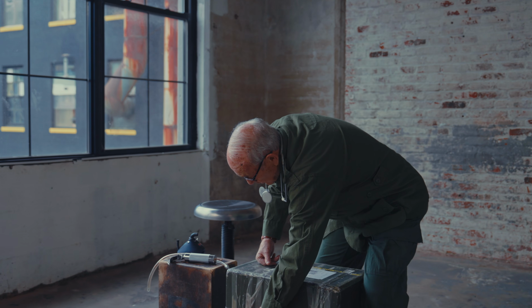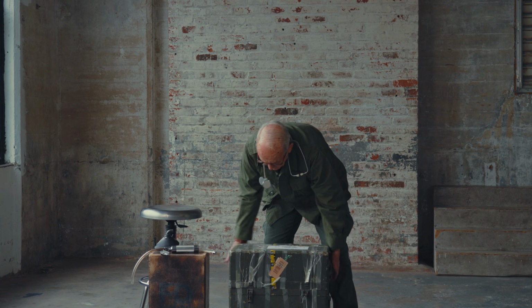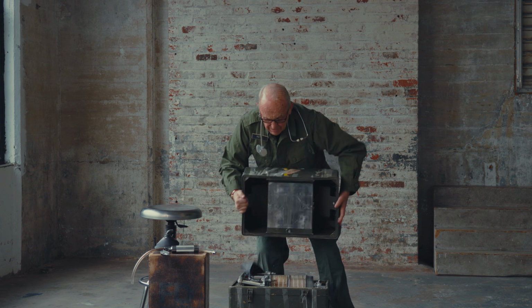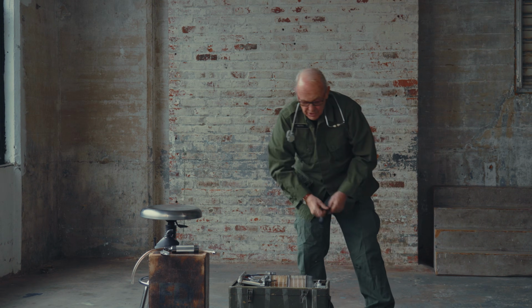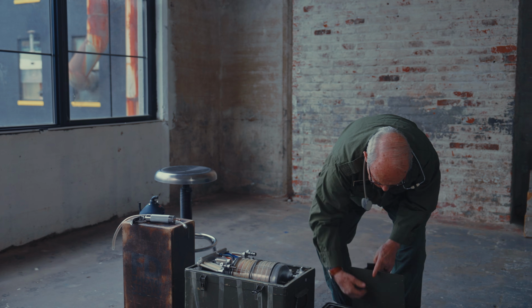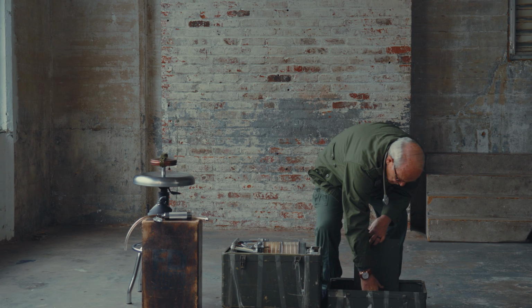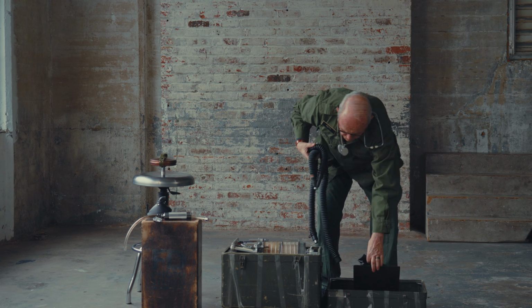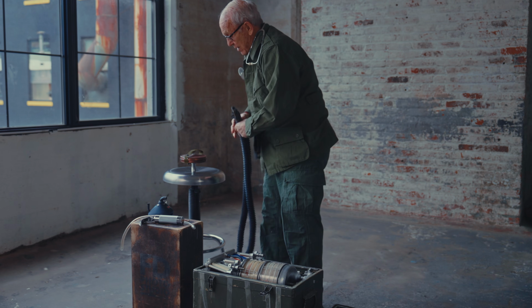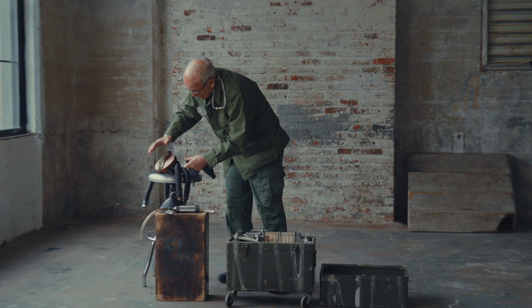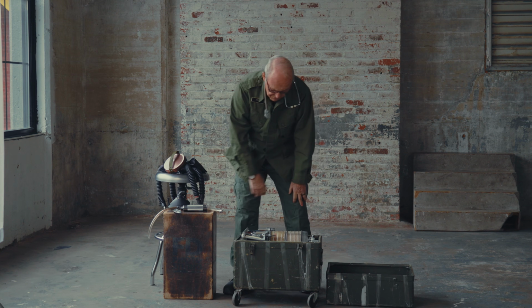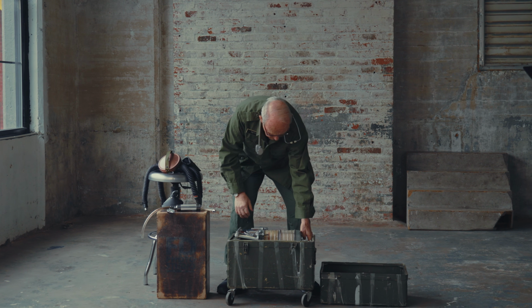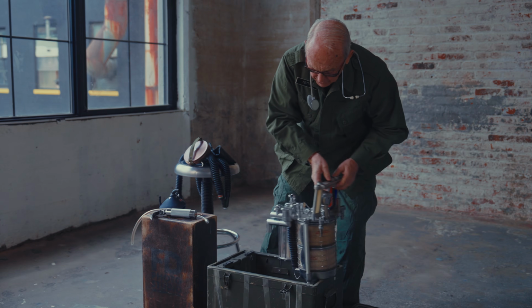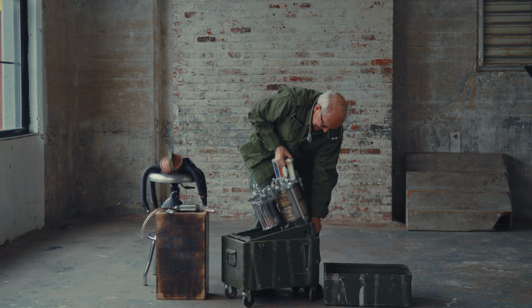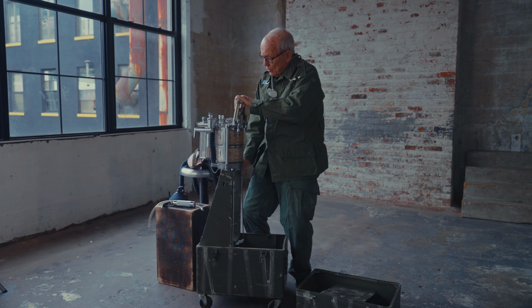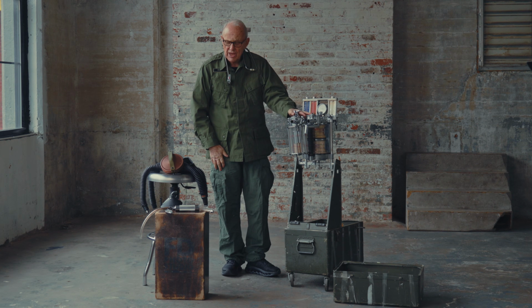First of all, you have to undo snaps that hold this top on both sides. Then you lift this up so it divides it into two pieces. In this piece over here is stored the respirator, which we will demonstrate in a moment, and it holds the tubes that carry the air and the anesthetic to the patient. We'll assemble those in just a moment. In this half is the operation port of the field anesthesia machine, and it pulls up in one section. It has a knob that holds this. This is the working part of the anesthesia machine.